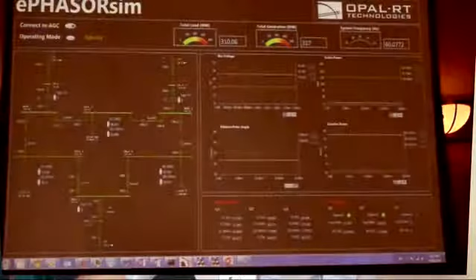We decided to use OPC for this demonstration just as a choice. A lot of times customers will have existing SCADA systems already, and we just make an OPC connection just like they're collecting the data. But we also have direct 61850 drivers and DNP3 drivers that can be configured to talk to the two systems. Okay, so right now you see that the system is stable—the frequency is almost 60 hertz here.